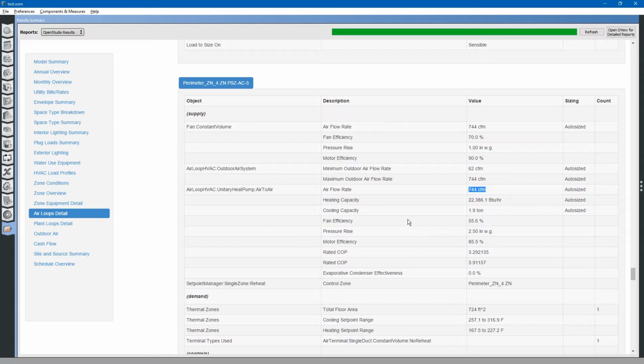And that is because EnergyPlus does autosizing based on the loop itself, and it doesn't take into account any external air balancing. And that's an important part of EnergyPlus. It does some air balancing, but it doesn't do all air balancing. So you need to make sure that your system is balanced for yourself. Now, it does account for this during the simulation because of that coupled toggle switch that we selected on the exhaust fan.